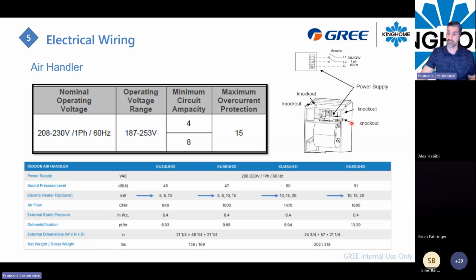So the air handler, you will have different knockouts, okay? One to bring the low voltage wire, your 24 volt wire, and you will have another knockout for your high voltage. In the case that you don't use electric heater, well, you have a terminal block that can receive your L1, L2, and the ground. And so because you don't use electric heater, you just have to provide a 15 amp breaker with a 2 15 wire gauge, 240 volts. Make sure that you will apply power to that board right here in the blower, and that's it.